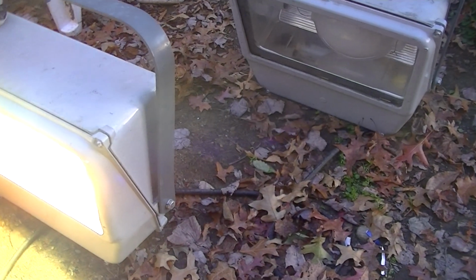So, just a simple test of one of these 1 kilowatt high pressure mercury floods. A comment I posted on the guts video of one of these, I think it was that one, said that you can also use M47 1 kilowatt metal halide lamps in these fixtures as well, as long as the open circuit potential of the ballast is at least 440 volts. And it's an M47 lamp in there. And it is clearly working. Also bright. But again, it's like 110, 120 something kilolumens from that one lamp. So yeah.